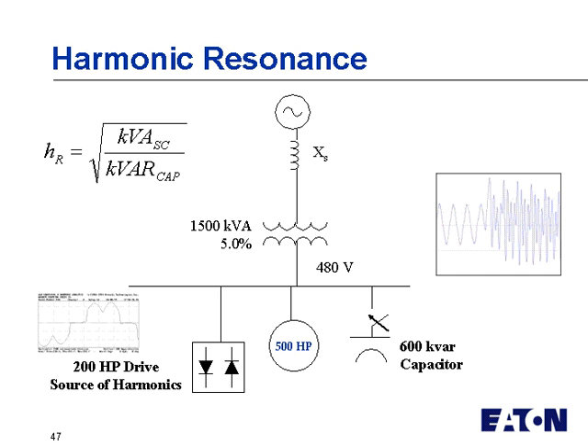Again, as an example, if you have a 200 horsepower drive down on the bottom left and you have normal motors on the system, but you add a capacitor bank to that system, a 600 kVAR capacitor, you can use this formula and these equations, which are the subject of a whole other webinar, to actually go through and analyze and figure out that the resonant point is close to one of the frequencies generated by that drive. In this case, it could be close to the 7th harmonic.